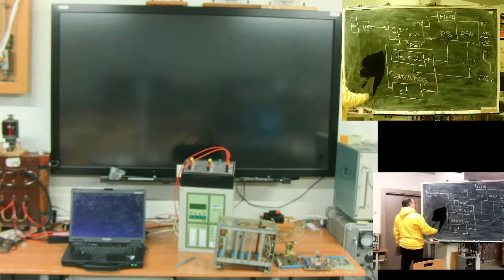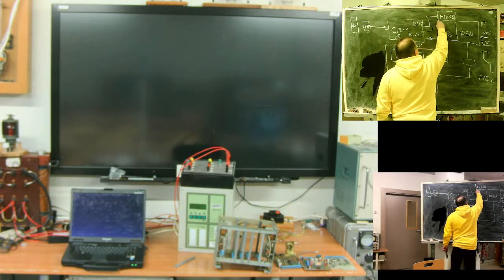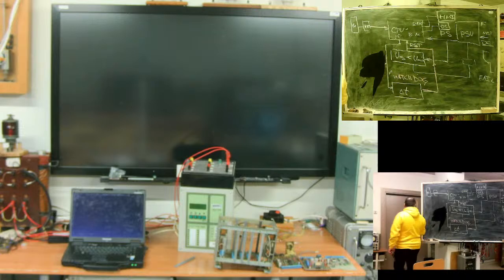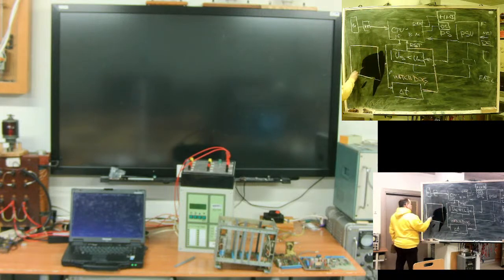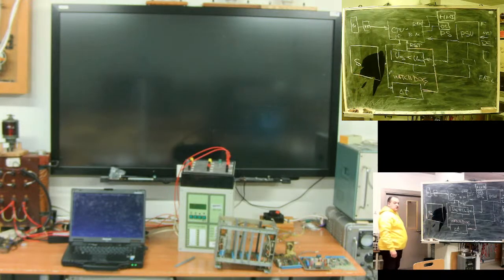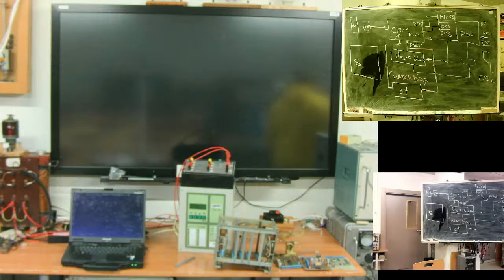And here comes one of the important parts of the device. So HMI, DC, data communication, should be somewhere. But here is a large part, I can mark it with a giant S. What's S? S is for settings. We need to store constants, many constants. Constants, thresholds. What is fault, what is not fault? Parameters of our object, also line resistance, capacitance, maybe something more, and some service constants, like baud rate.